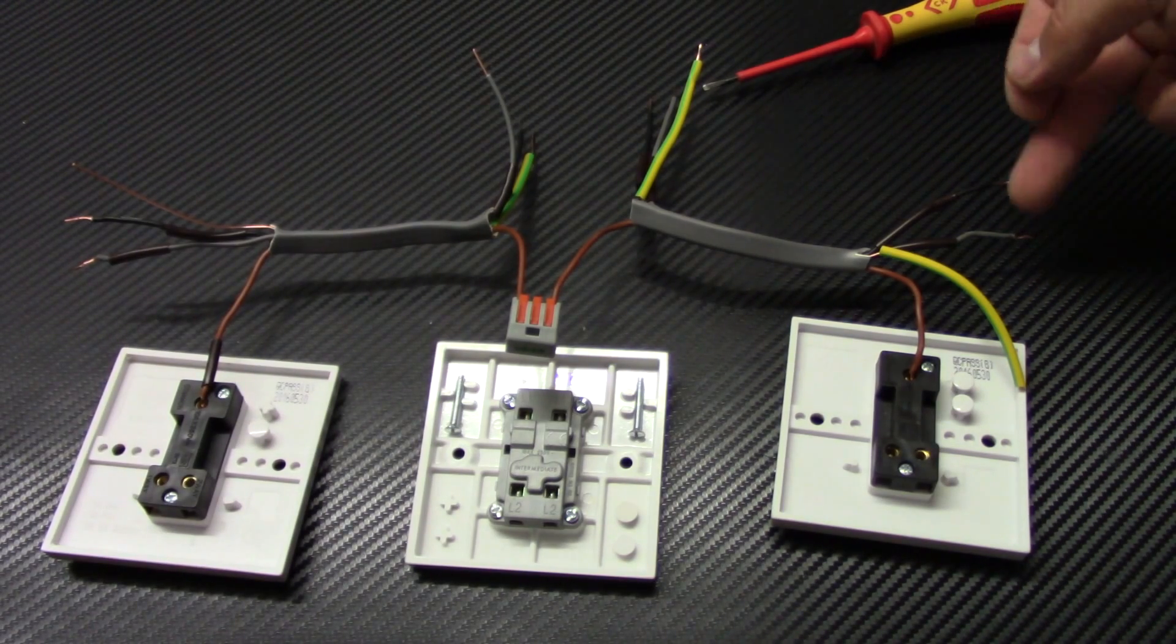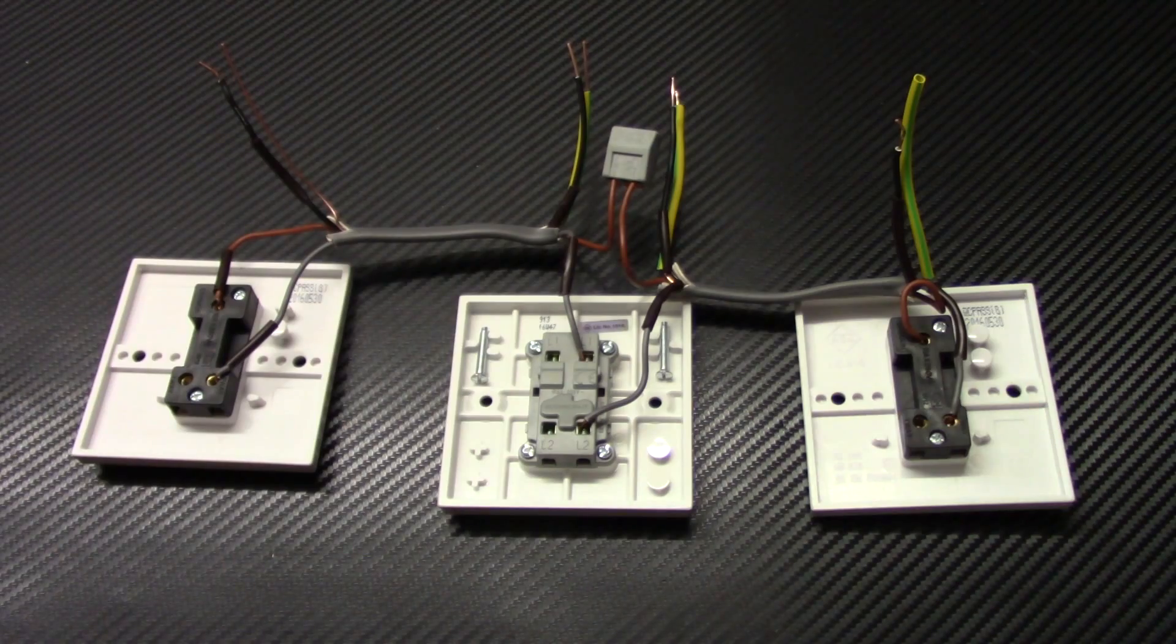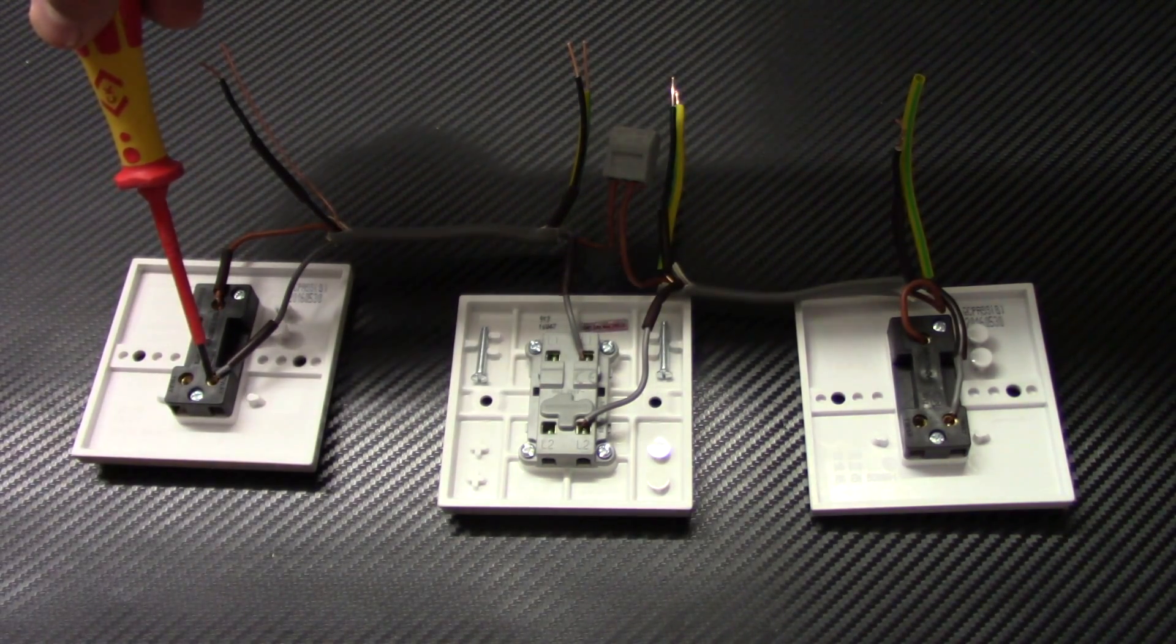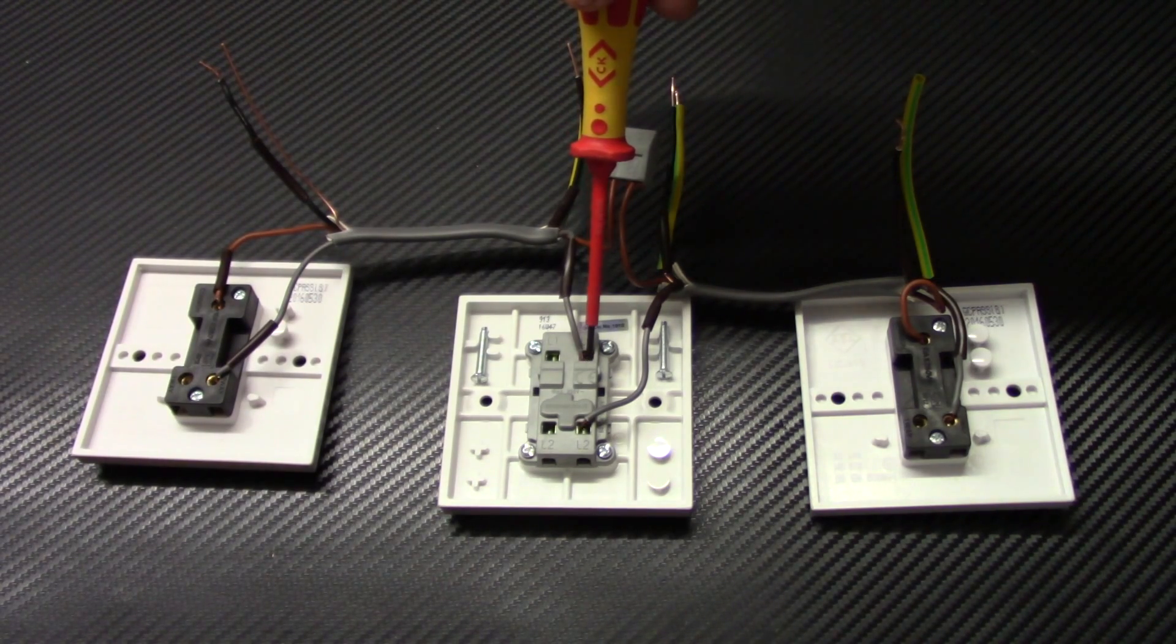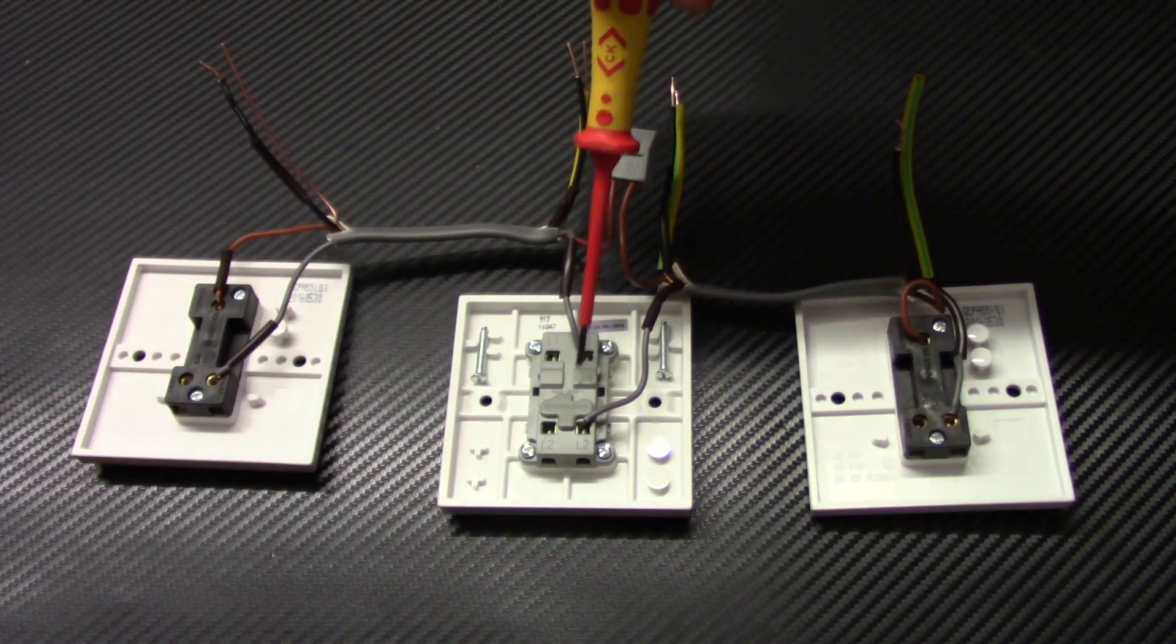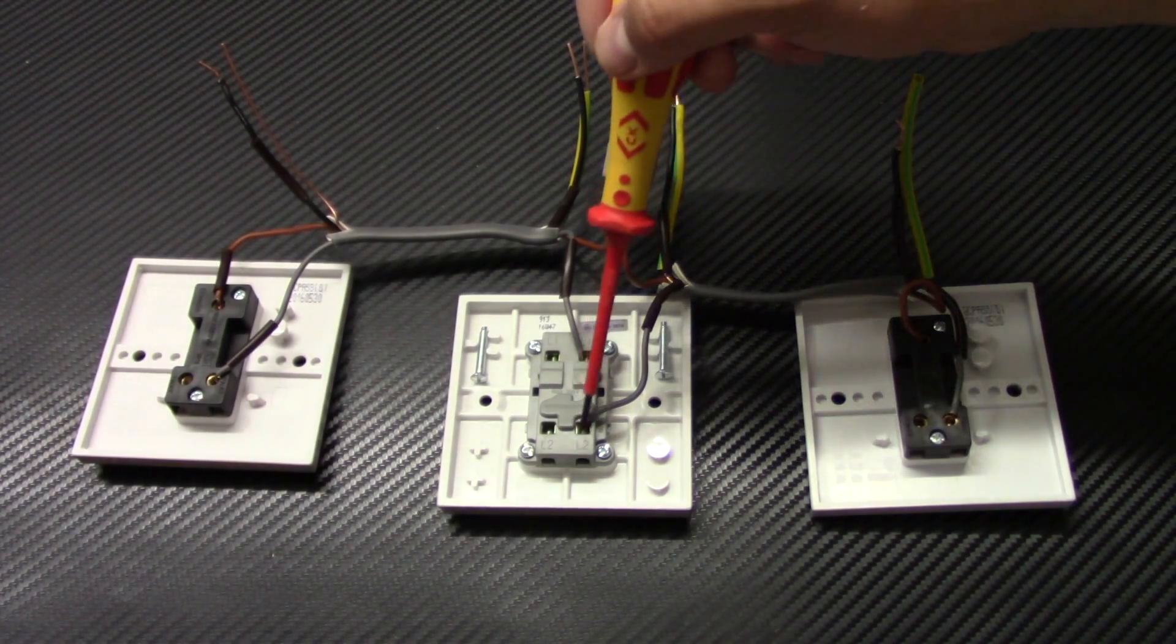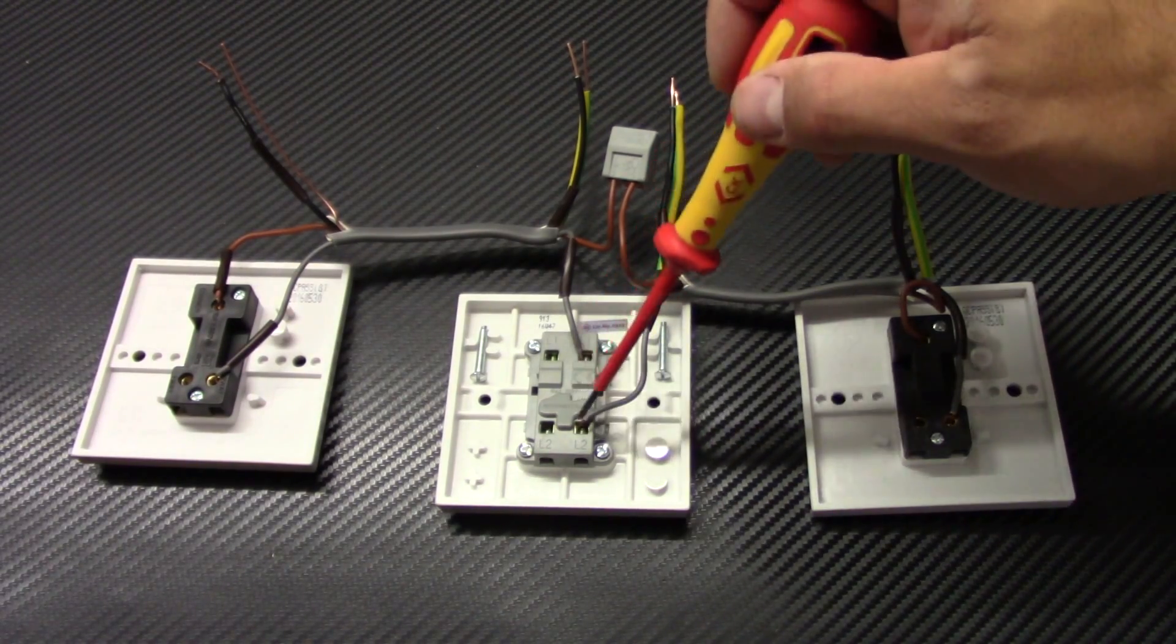Now let's do the grey wire. From the first switch the grey wire is connected to L2 terminal. Then intermediate switch L1 terminal. And then I connected the grey wire opposite on the L2. And from this one is connected to the L2 as well. So L2, L2, L1, L2. This has to be opposite.